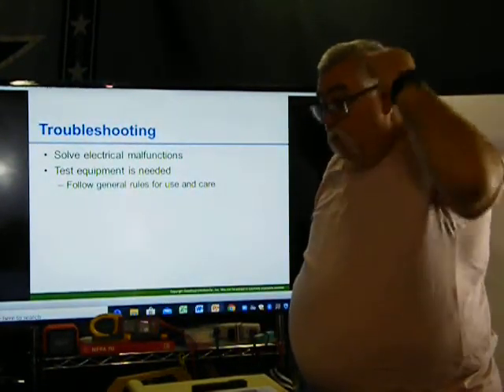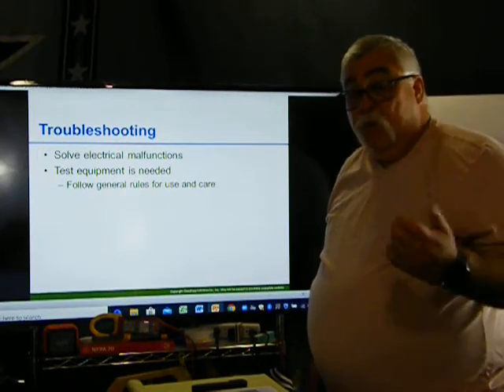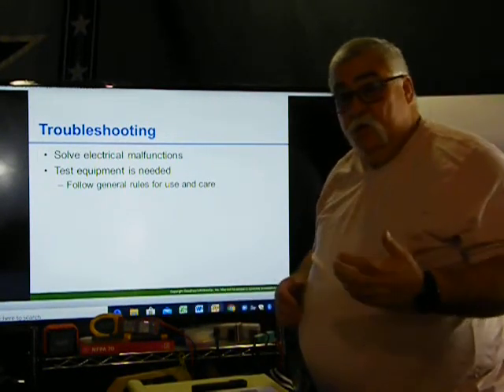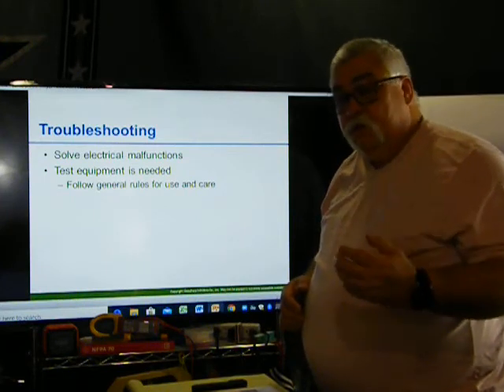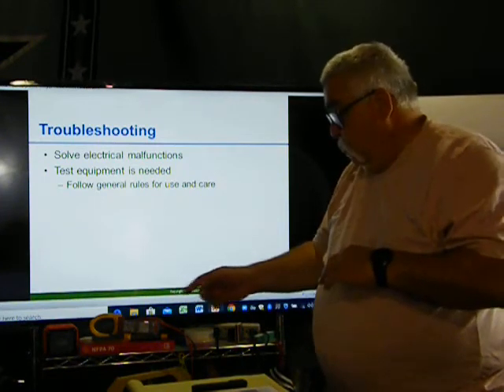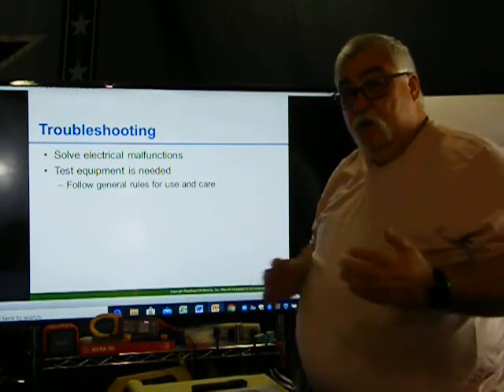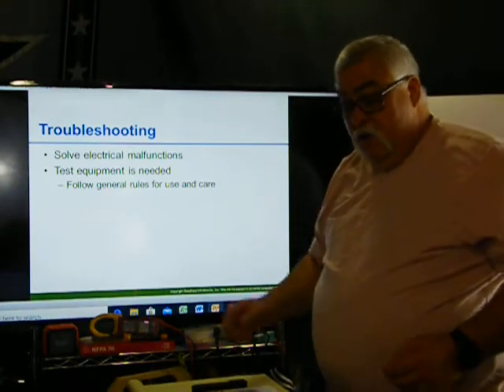I have a couple of smaller amp probes, and those are only rated at 100 amps because they're smaller. Okay, voltage is 600 volts, but the amperage is 100. That one goes up to 1000. I don't want to go over 100 amps and use it.